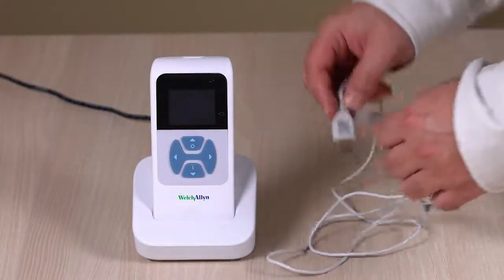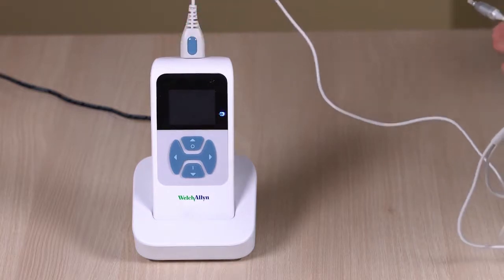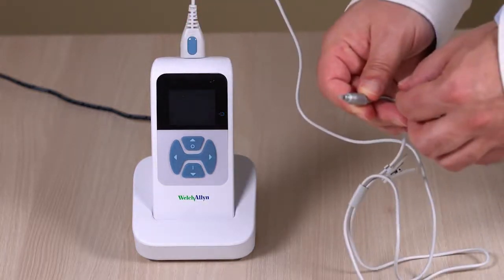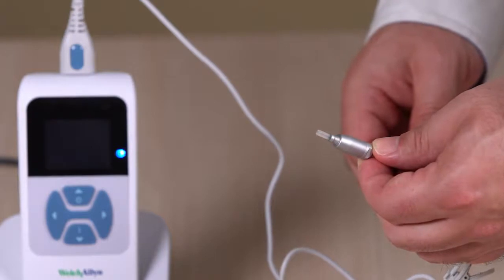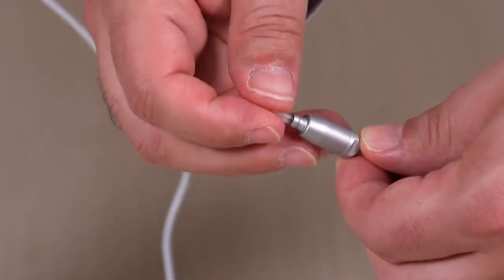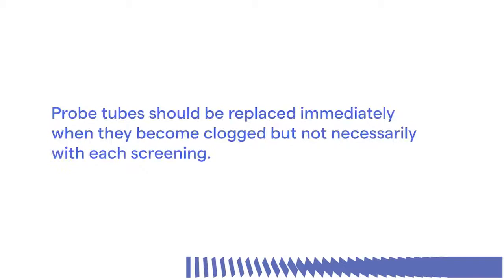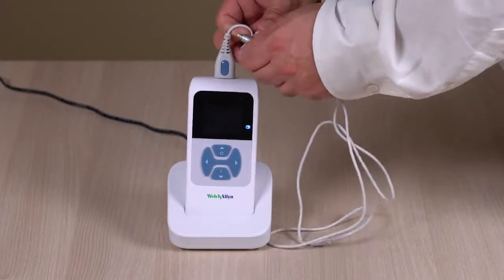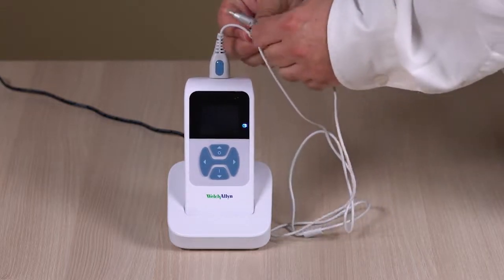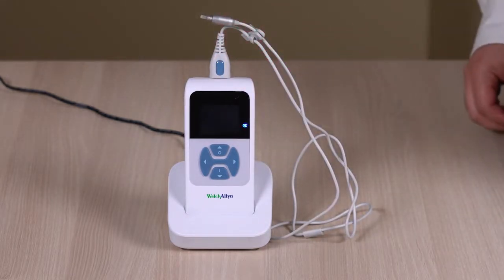Next, install the probe. Insert the probe connector into the socket on the top of the screener. A clear probe tube must be attached to the probe head before an ear tip is applied. Insert a new probe tube into the probe head until it is fully seated and snaps securely into place. To remove the probe tube, grasp the tube and pull gently away from the probe head with a slight twist. Probe tubes should be replaced immediately when they become clogged, but not necessarily with each screening. Finally, place the probe holder near the end of the probe cable, and gently press the probe cable into the probe holder close to the point of the probe head. Return the probe to the probe holder for safekeeping.